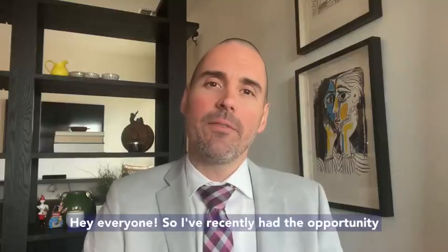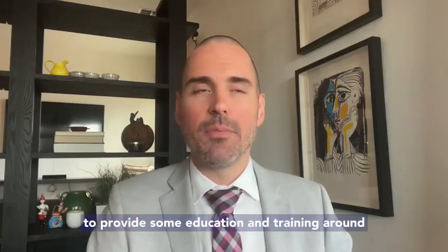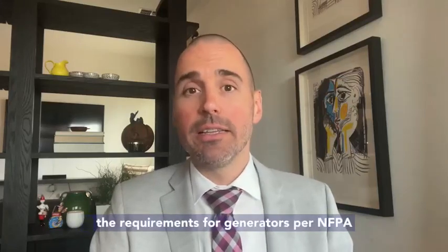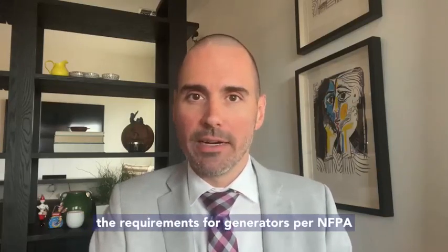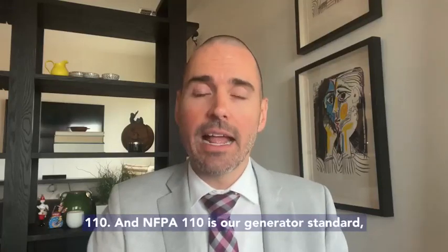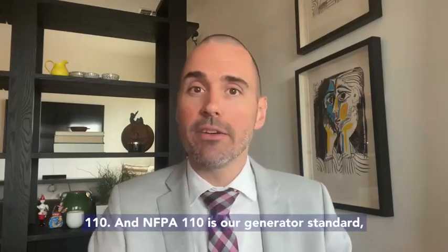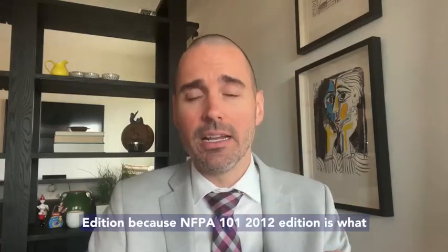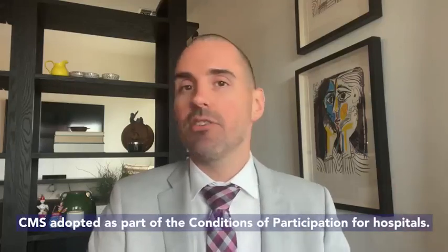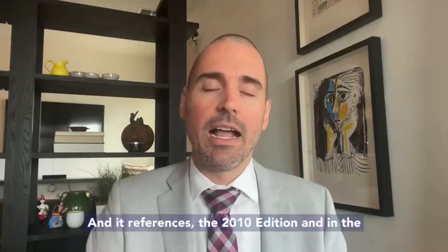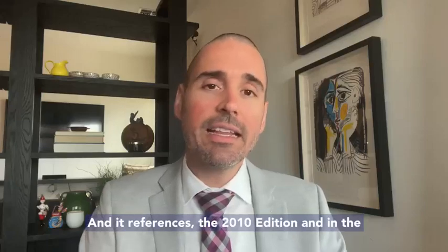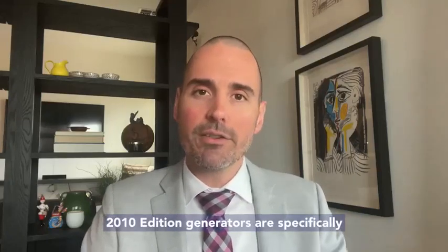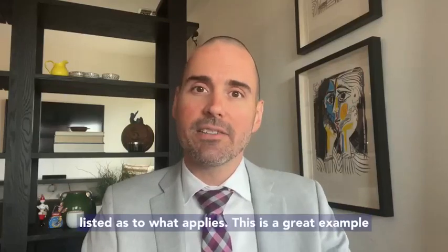Hey everyone. I've recently had the opportunity to provide some education and training around the requirements for generators per NFPA 110. NFPA 110 is our generator standard, our generator code. And we follow the 2010 edition because NFPA 101 2012 edition is what CMS adopted as part of the conditions of participation for hospitals, and it references the 2010 edition. In the 2010 edition, generators are specifically listed as to what applies.